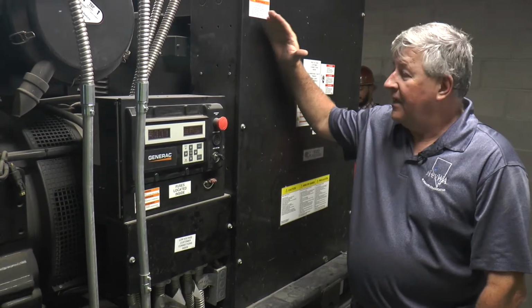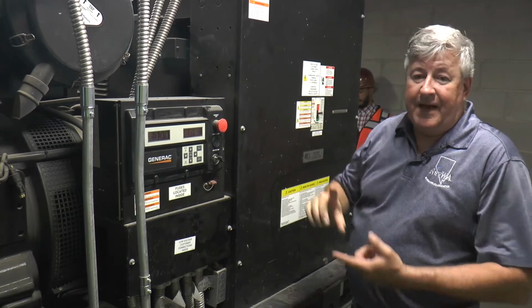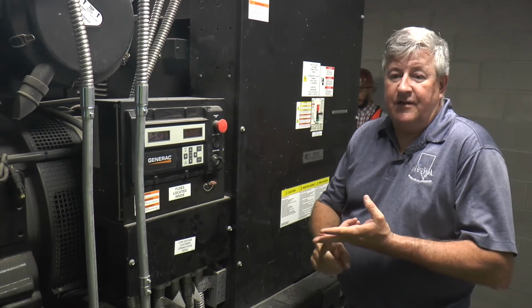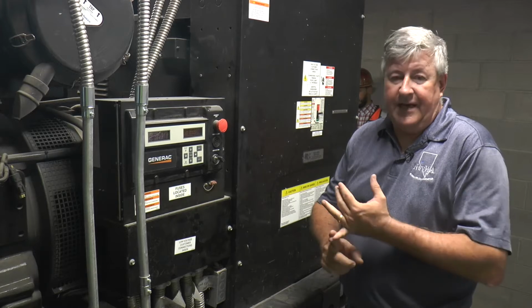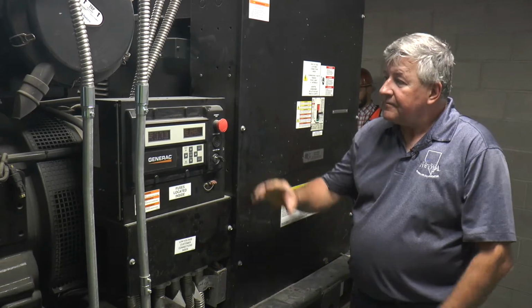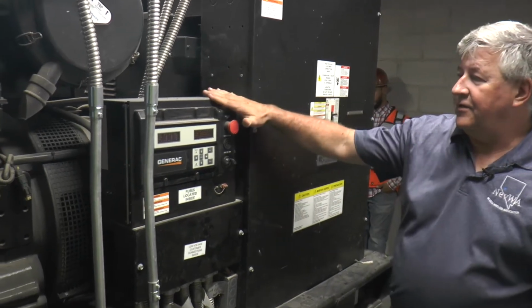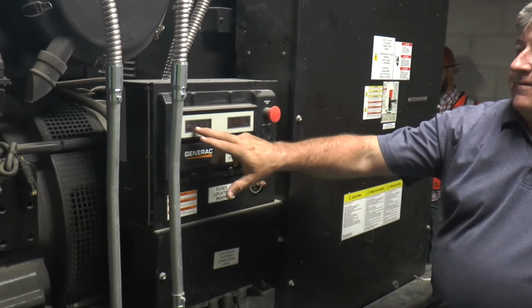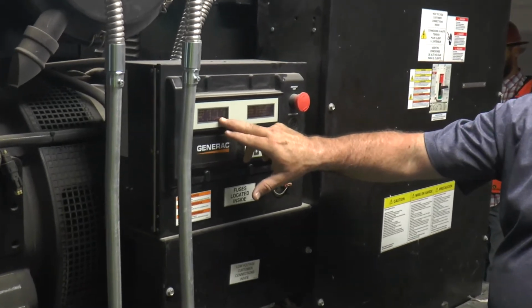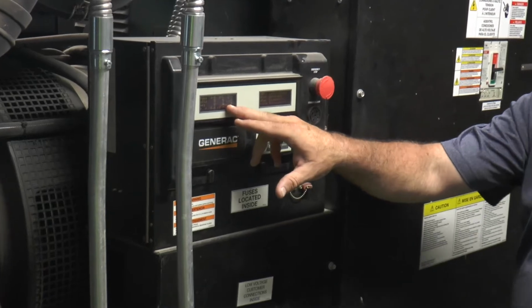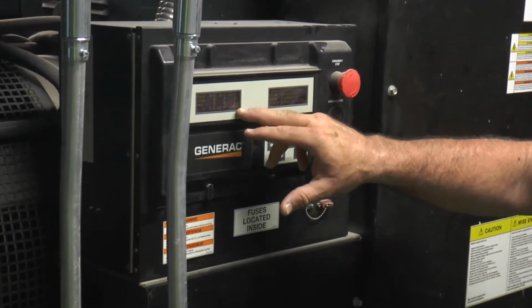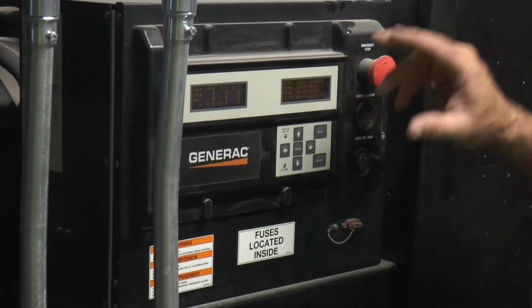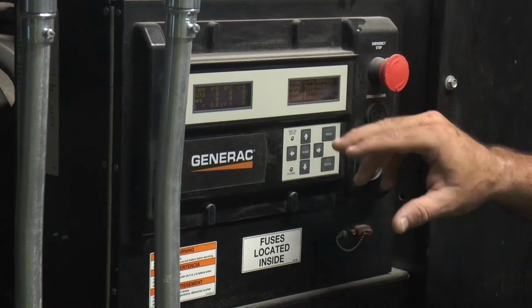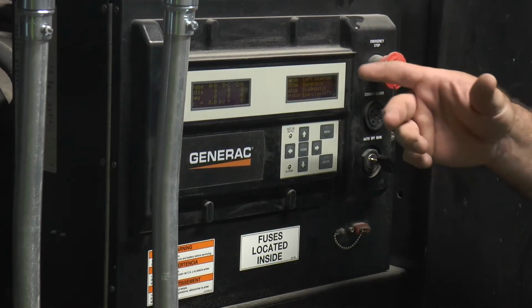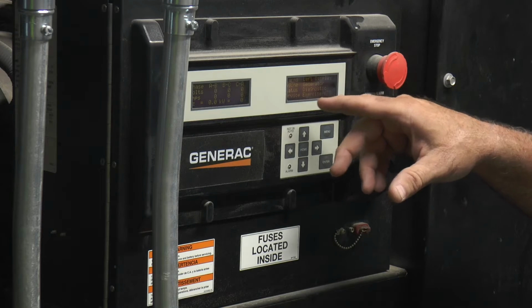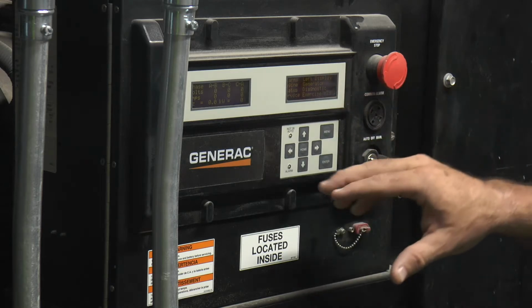the entire building. This generator is designed to back up 2 elevators, exhaust fans, fire pump, and egress lighting for this building. On the generator set, we have the engine controller. The first screen is the display for alternator parameters, which gives you voltage, amperage, current, and kW. The second screen is our display screen that's going to give you generator alarms, engine conditions, status of the equipment, status of the generator set.